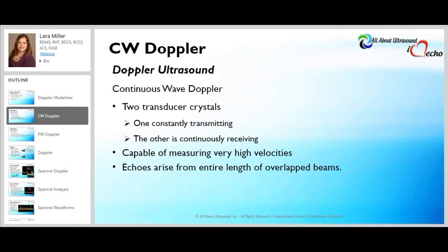For continuous wave Doppler, there are two transducer crystals — one is constantly transmitting while the other is constantly receiving. With continuous wave, there's no damping. It has a narrow bandwidth and a high Q, and because of that, it has the advantage of higher sensitivity in detecting small Doppler shifts as well as measuring very high velocities. However, the echoes arise from the entire length of the overlapping beams, and so there is range ambiguity.